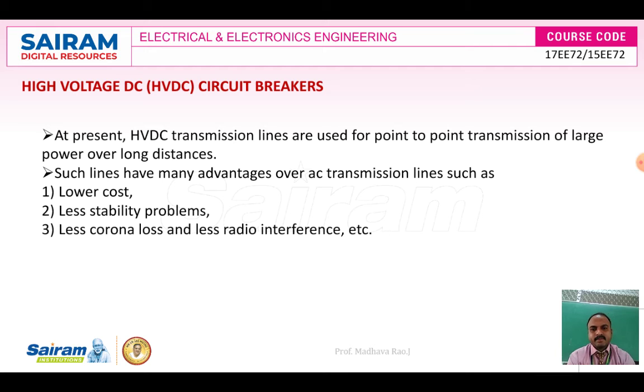At present, HVDC transmission lines are used for point to point transmission of large power over long distances. Over long distance you can use them to reduce the I square R losses, that is the copper losses, and to reduce the conductor cost and the transmission tower cost. So we are moving to HVDC transmission. When you are transmitting HVDC power, we need HVDC circuit breakers, right? So these HVDC circuit breakers we use in HVDC transmission.